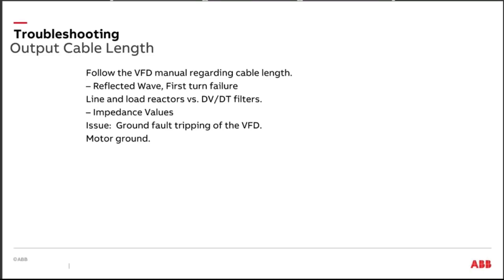Sometimes we might use nothing but a load reactor in the output of the device. As a general rule, I kind of like a dV/dt filter. It puts a fairly low amount of impedance in that output circuit. And we also have a low pass filter, a capacitor and a resistor in there. And it really helps clean the top of the PWM waveform up. It really looks good when you look at it with a scope. So I kind of lean towards a dV/dt filter in the output of the drive when I know I'm going to have a longer motor lead.